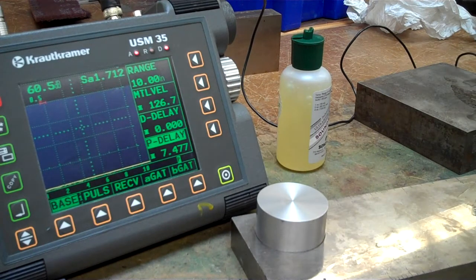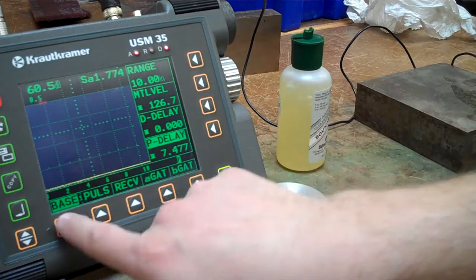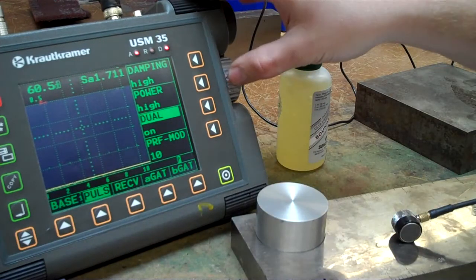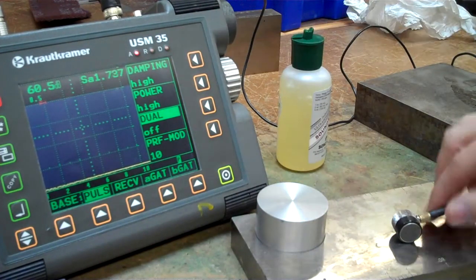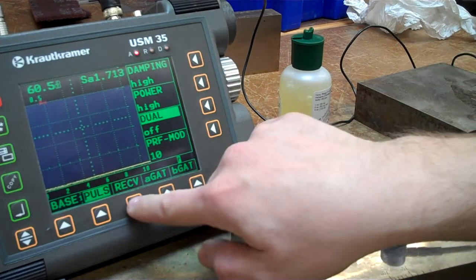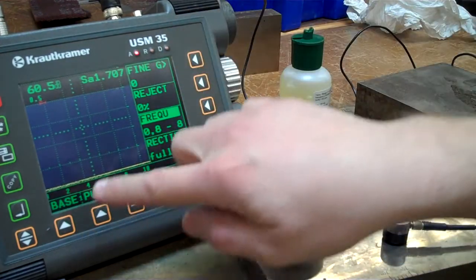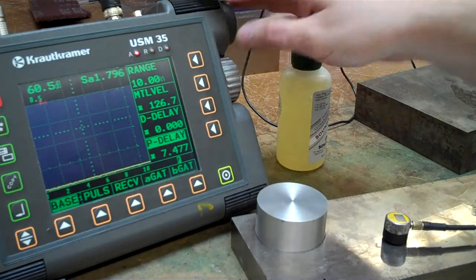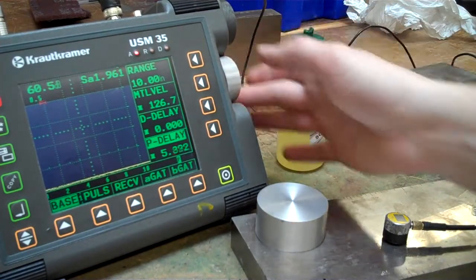I went back to a single element transducer, so we need to turn the dual element off. Go to the pulser, turn the dual off. We have a 2¼ megahertz, so let's go to receiver. Go back to our base menu and bring our probe delay all the way to 0.